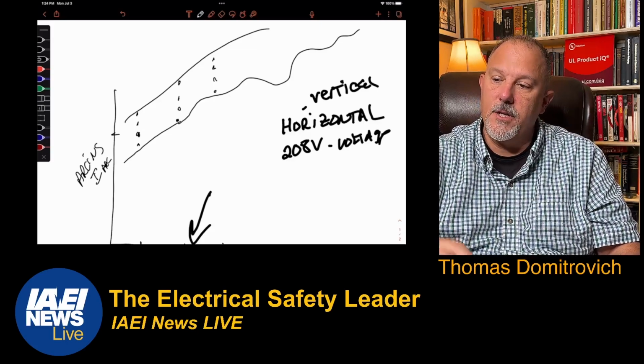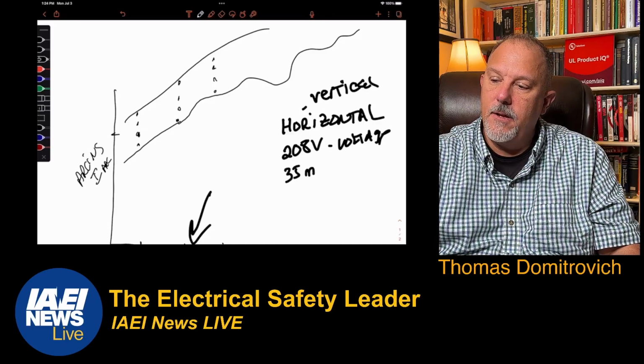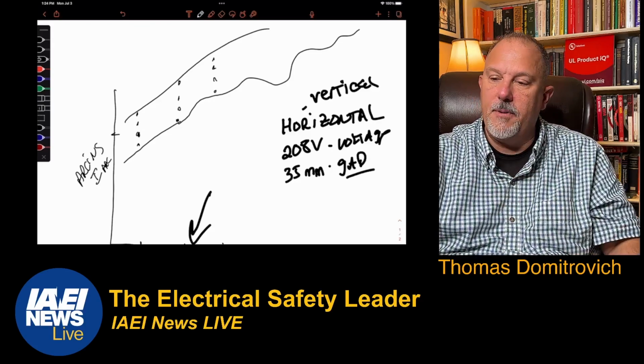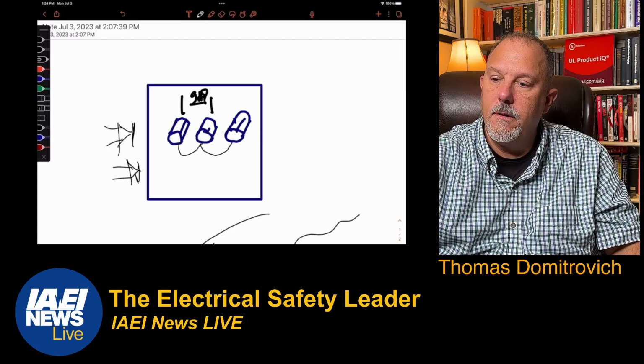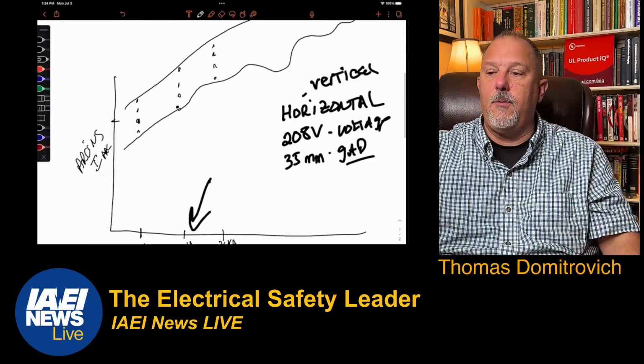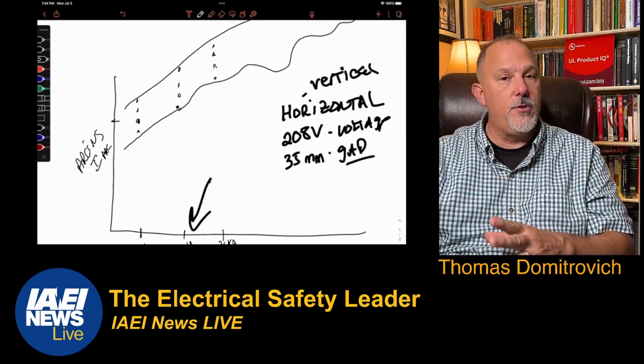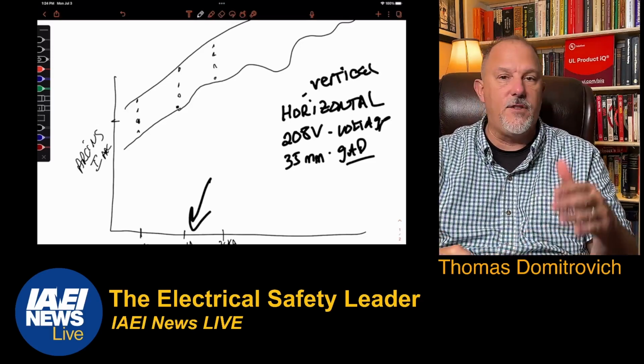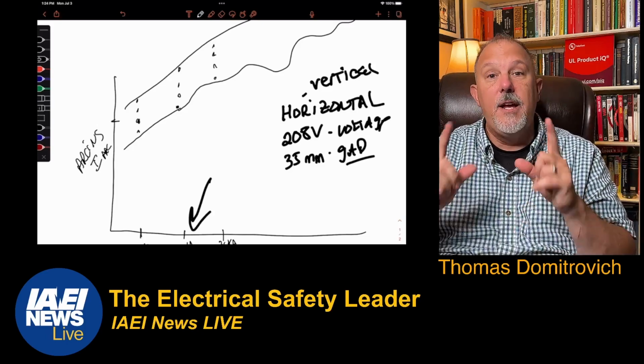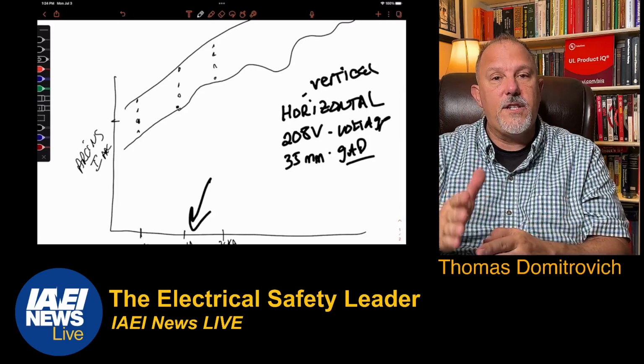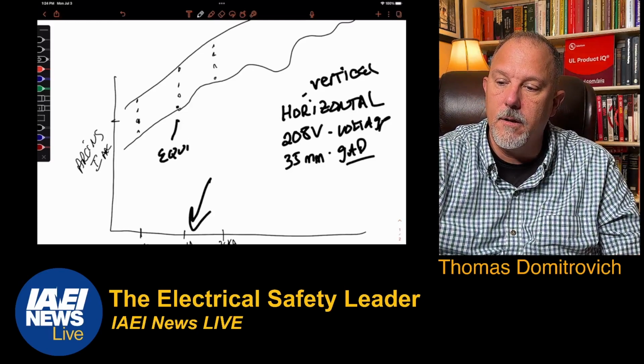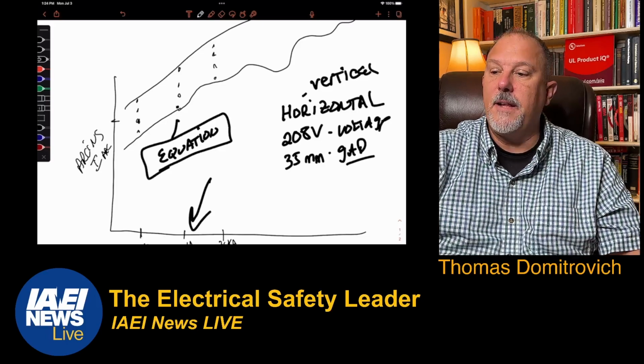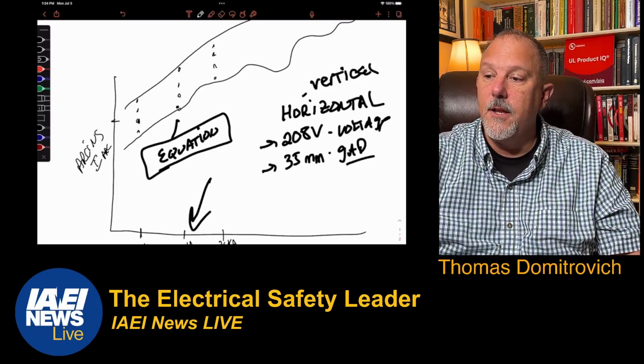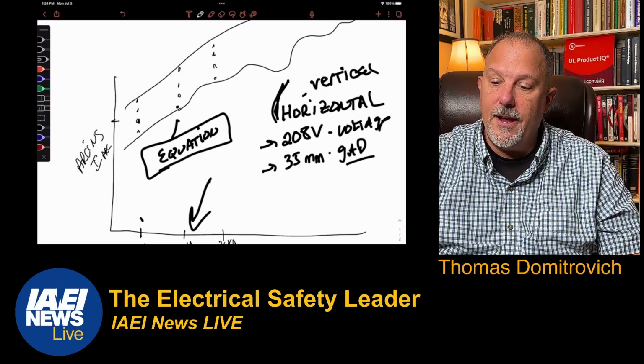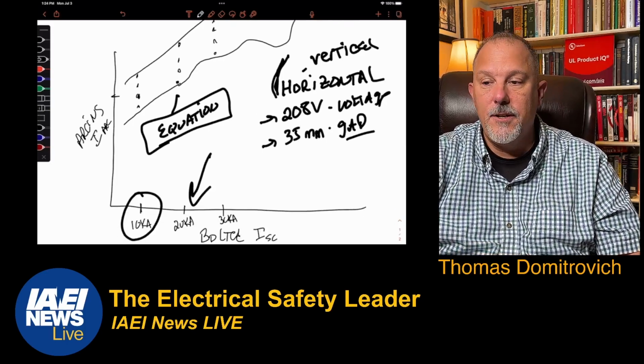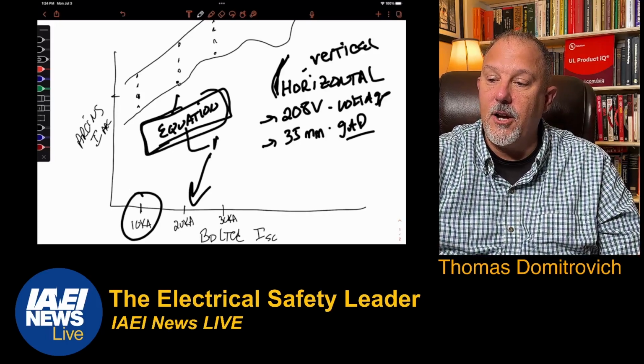Trying to think if there's anything else. A gap, maybe, I don't know, say it's 35 millimeter gap. And that's the gap in between these electrodes. So there's parameters. And you may say, well, I'm going to change my voltage to 480, and now you'll have a whole another set of curves. And you may say, I'm going to change my gap from 35 to 25, and then you'll have a whole nother set of a similar curve. But the bottom line is that you have a series of lines, and I can create an equation that takes in the voltage consideration, the gap consideration, the electrode configuration consideration, and your available fault current as a consideration. So we create an equation to calculate arcing current.